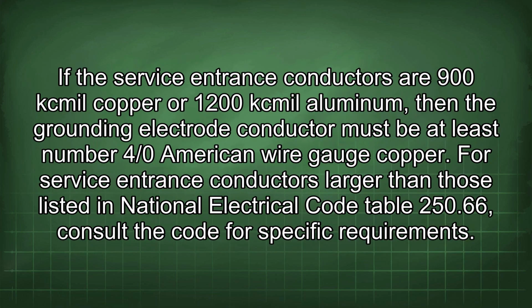If the service entrance conductors are 900 kcmil copper or 1200 kcmil aluminum, then the grounding electrode conductor must be at least number 4/0 American wire gauge copper. For service entrance conductors larger than those listed in National Electrical Code Table 250.66, consult the code for specific requirements.